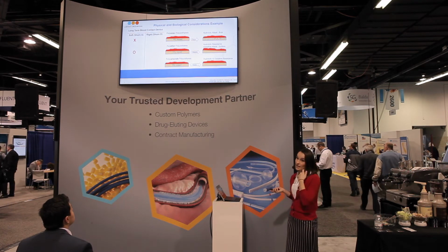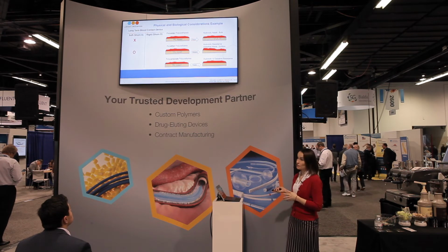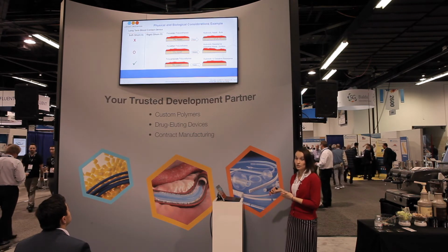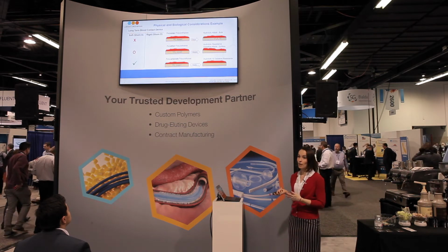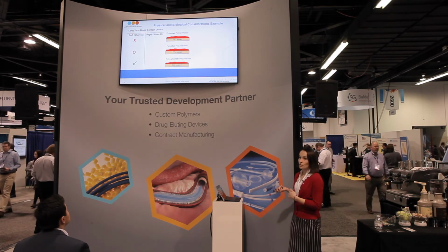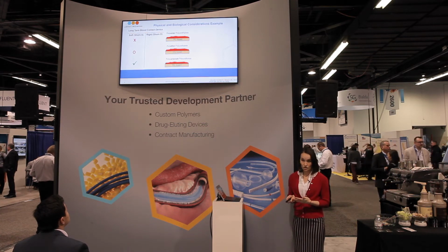So the last type is a polycarbonate-based polyurethane, and these products are both hydrolytically and oxidatively resistant, and they can resist attack from both water and blood cells in the months to years time frame. So these are typically a good one to start out with if you're looking for a flexible long-term blood contacting polyurethane.